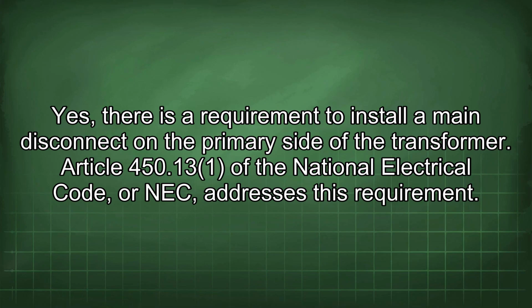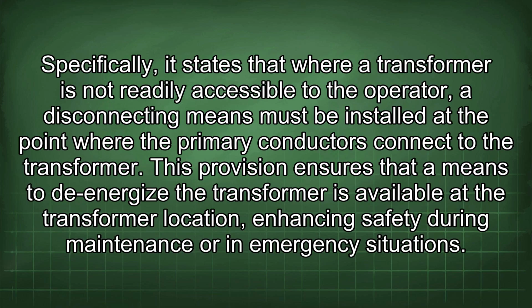Yes, there is a requirement to install a main disconnect on the primary side of the transformer. Article 450.13(1) of the National Electrical Code, or NEC, addresses this requirement. Specifically, it states that where a transformer is not readily accessible to the operator, a disconnecting means must be installed at the point where the primary conductors connect to the transformer.